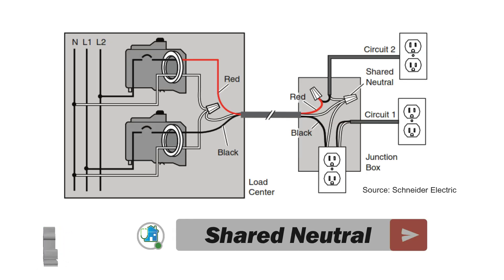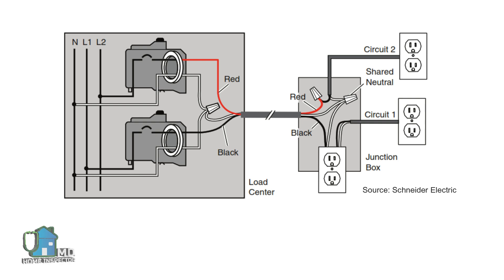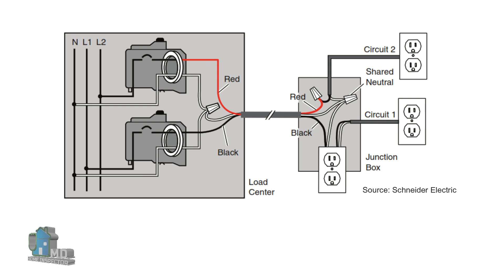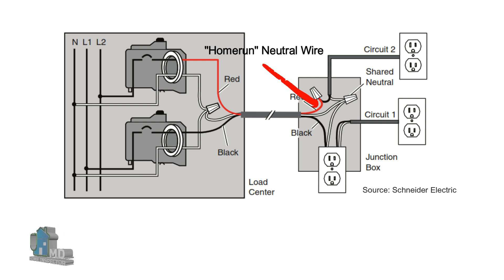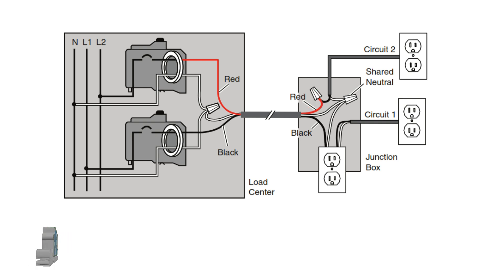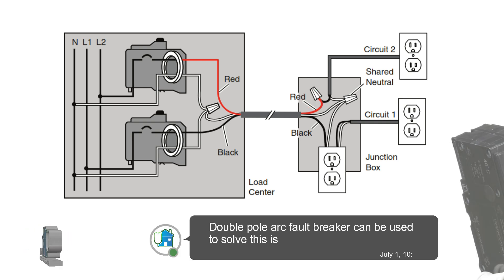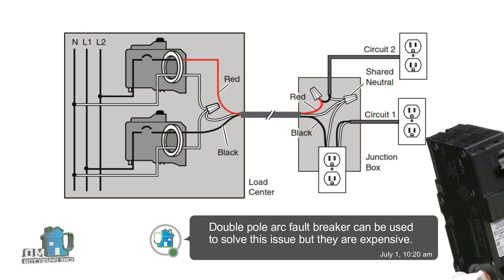A shared neutral is another issue. If an arc fault breaker is connected to a shared neutral, the single pole AFCI will not work properly. A shared neutral occurs when two circuits share a single home-run neutral wire back to the panel instead of running two separate neutral wires. This setup will not work with arc fault breakers, but one possible solution is to use a double pole arc fault breaker in its place.